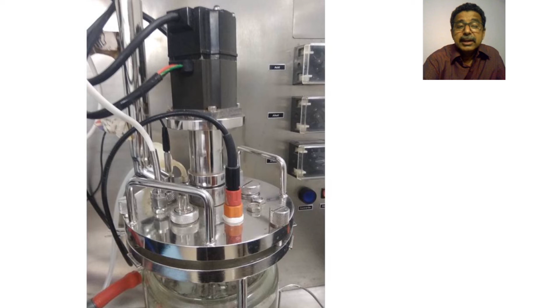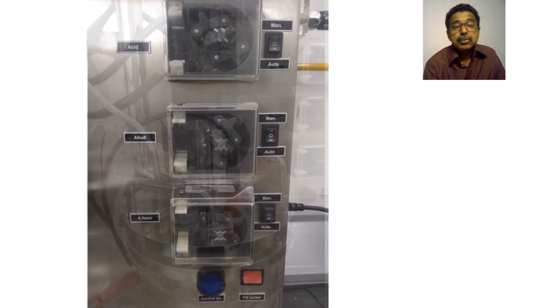The RPM of the motor is also controlled by the control unit only. The peristaltic pumps, as I said, are for alkali-acid, acid-alkali, and antifoam — these three only. All these switches are three-way switches: off, on, and auto. So you can select automatic function or manual function.